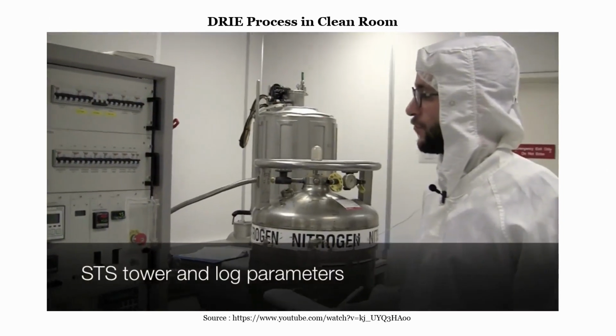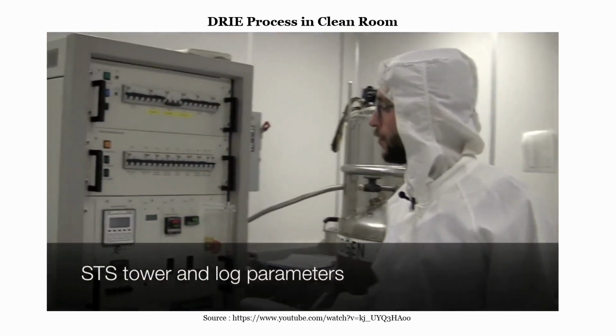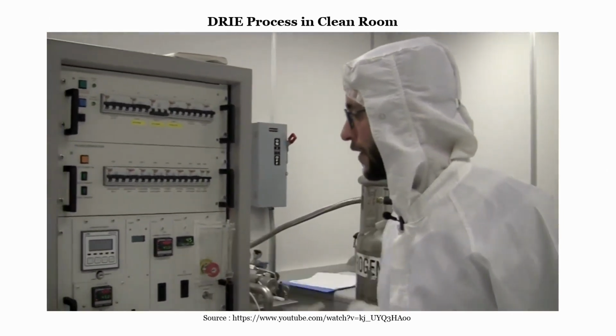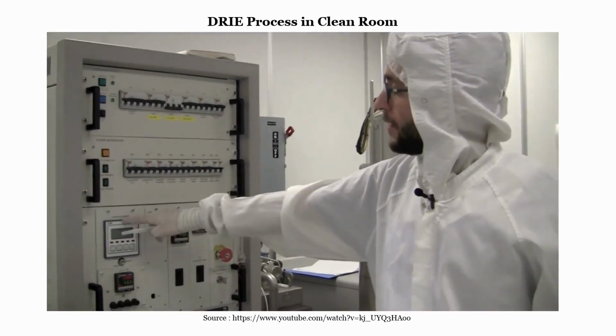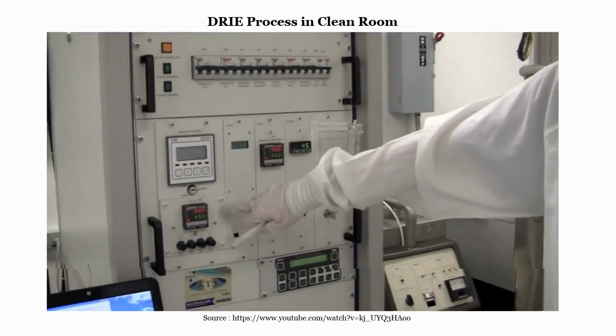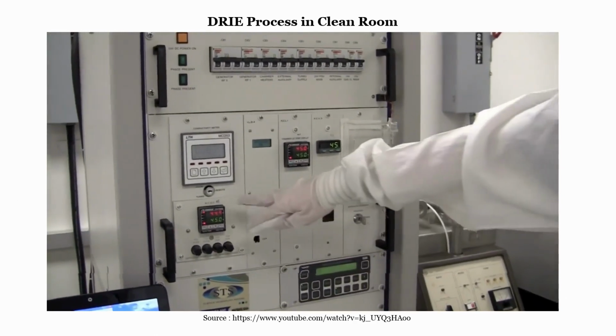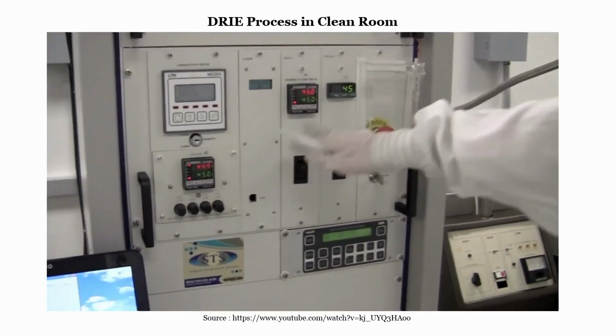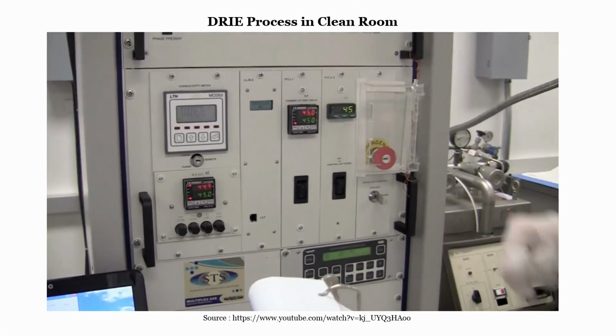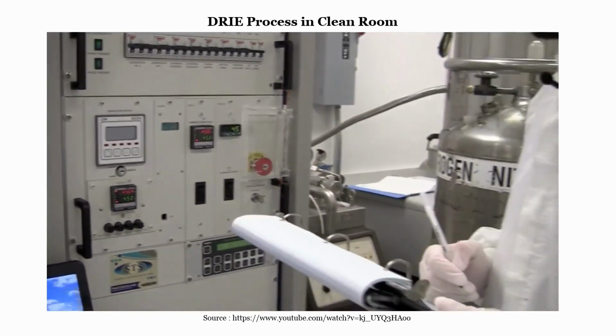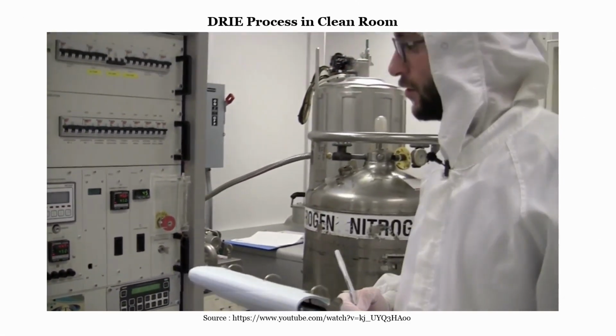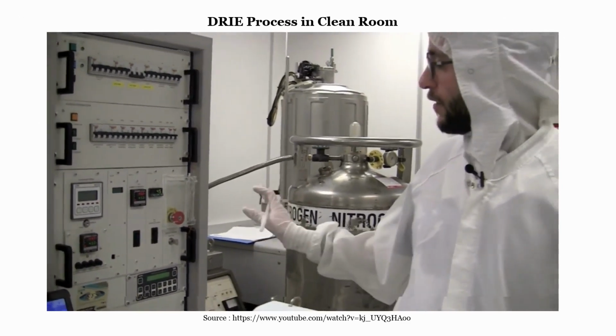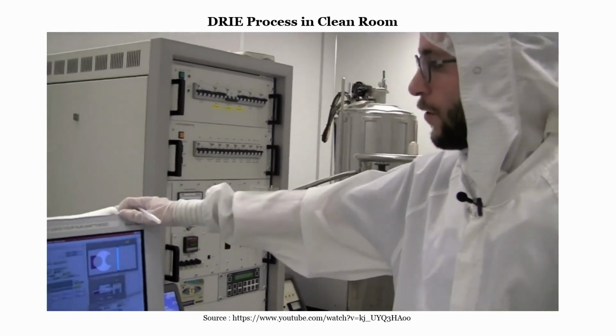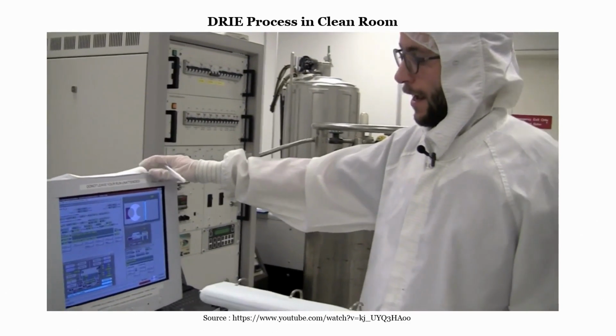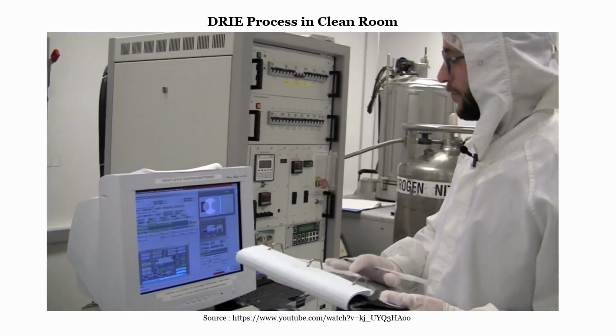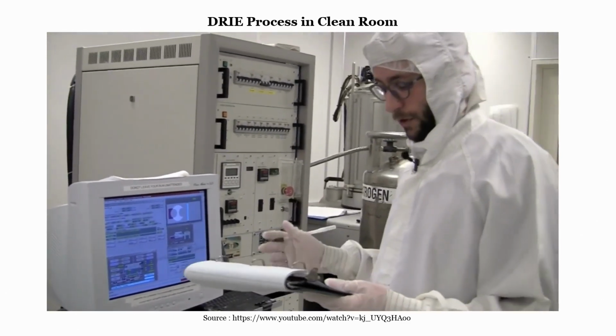Back in the STS room, the first thing that we will do is check the STS tower, and then we will record the conductivity of the water and the temperatures on the STS, the HCU 5, 3, and 1. Once we have recorded the values from the tower, we will go to the computer to record the other values.